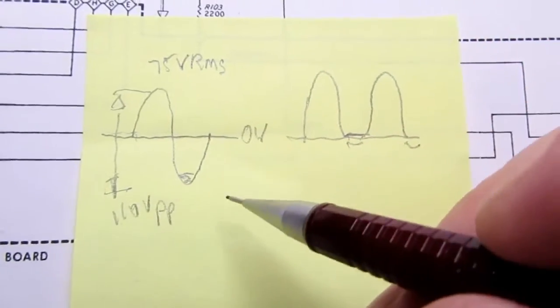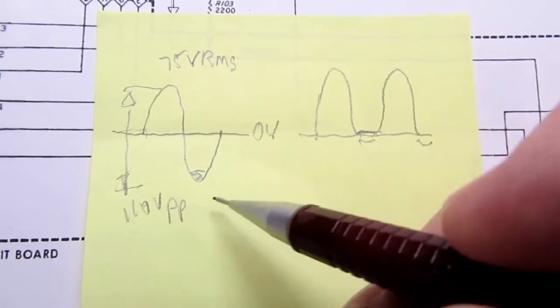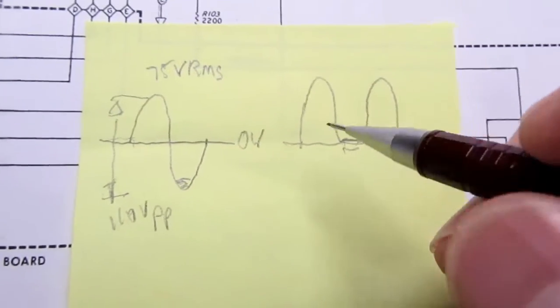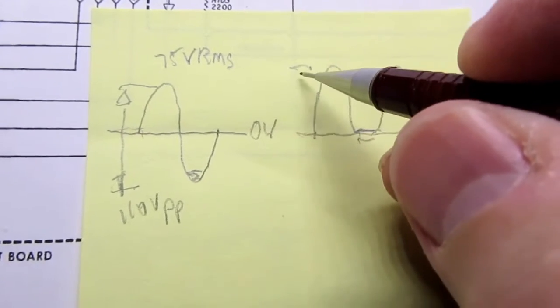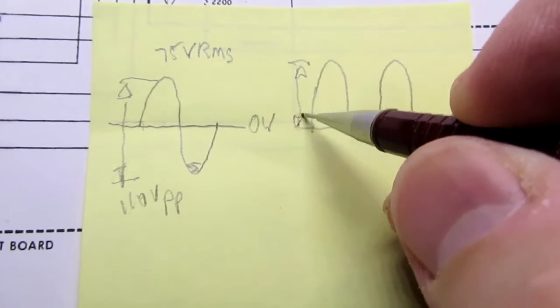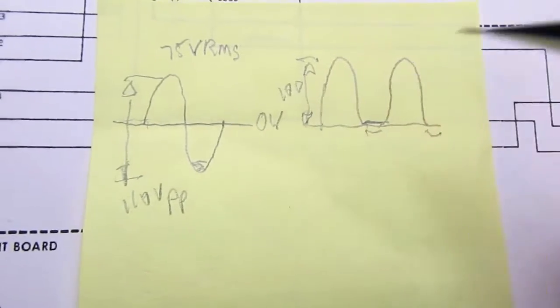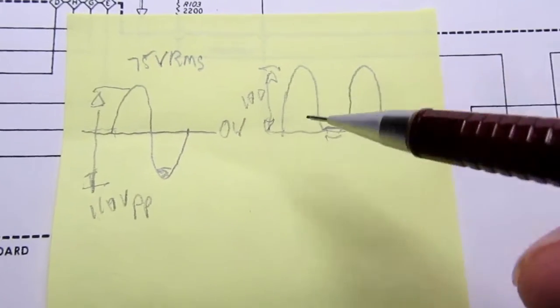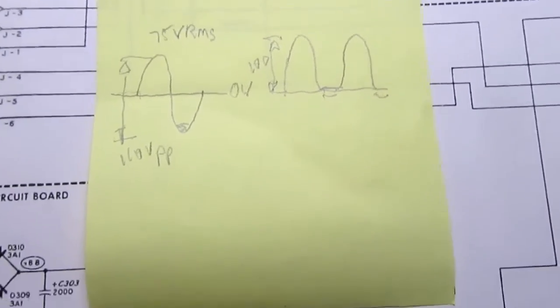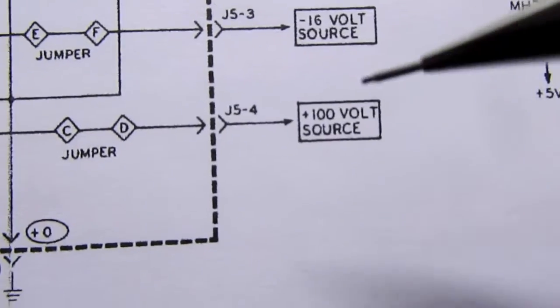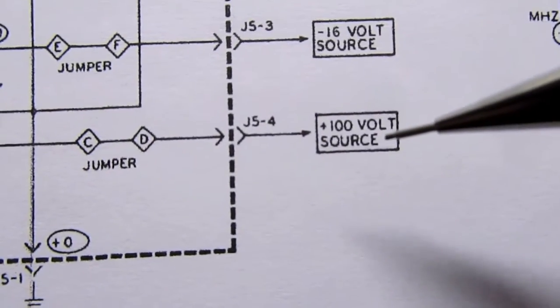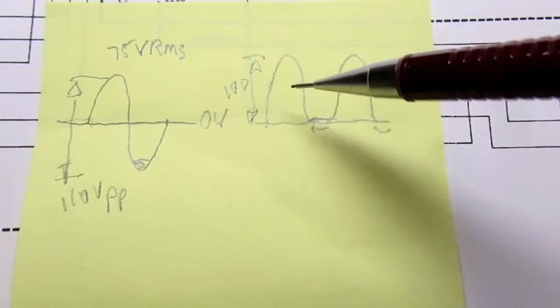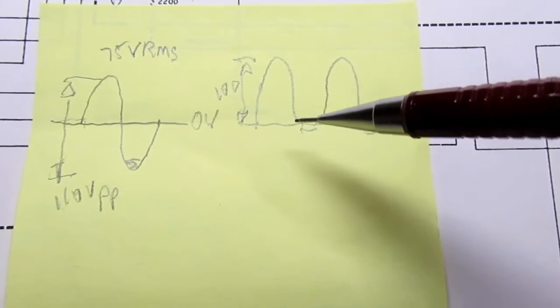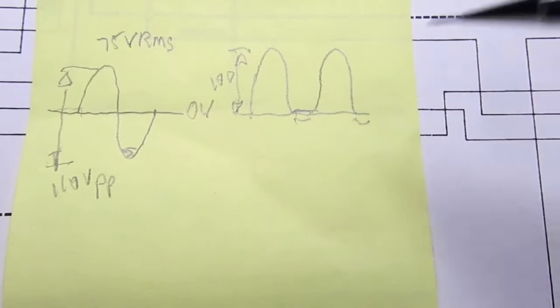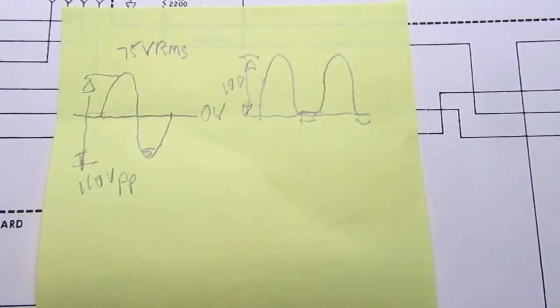So let's round that off and say we've lost 10 volts of the 110 volts from the clipping. So that would make that pulsing voltage from here to here about 100 volts peak. And indeed, they're calling it a 100 volt source. They just don't mention that it's a highly pulsed source, not at all smoothed off. It's on for about half the waveform, a bit more than that, and then off and then back on. So that's what's going on there.